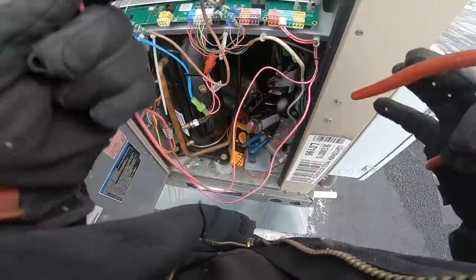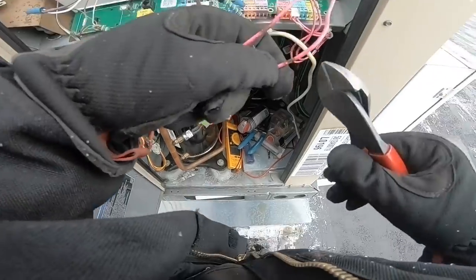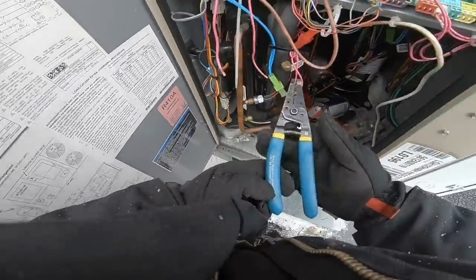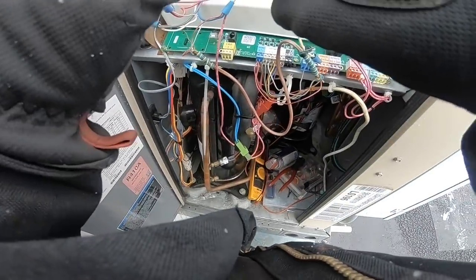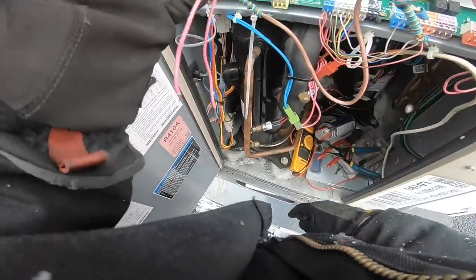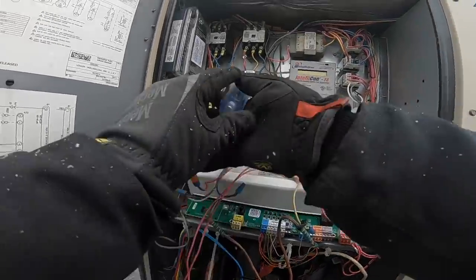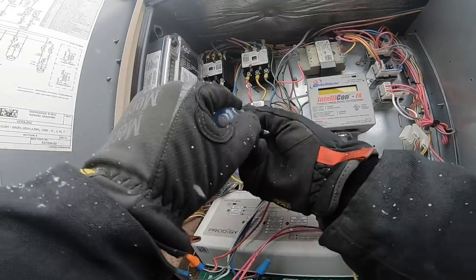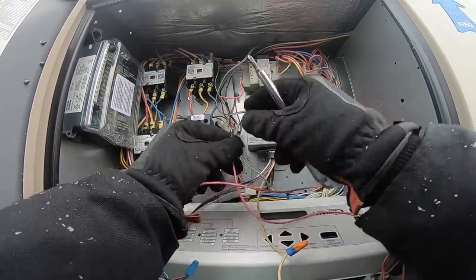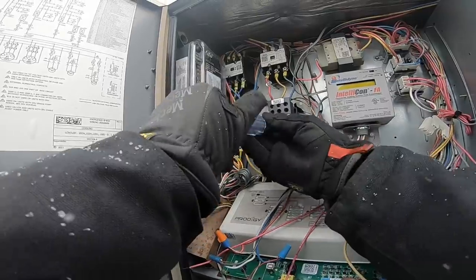Fix these wires. I want to come up and over. I know I should go around, but I'm going to be taking a little bit of the wire off, so I'm going to cut these burns off right past it. See if I can splice and save that little bit of wire. If not, I can just go right on the other side. Yep, came right off. Sometimes when it burns, it welds and you can't get it apart. Those contacts are going through. I guess they're closed already. So let's open.